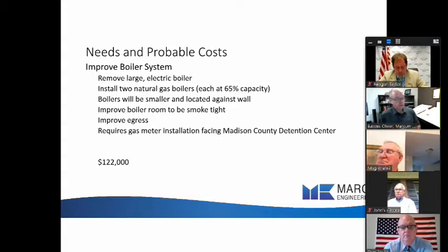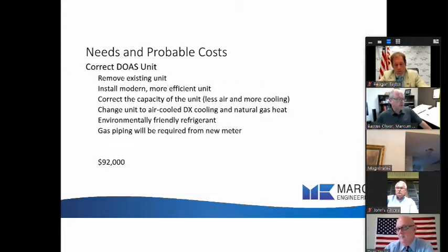The boilers will be smaller and they would be located against the wall, improving the egress and getting out of the NEC space requirements for the electrical panels. We'd also improve the boiler room to be smoke tight. And this would require a gas meter installation, and talking to the gas company, the best location we found for it was on the side of the building, the corner closest to the courthouse, and the meter would actually face our county detention center. So it'd be right along the sidewalk facing the detention center. To do this improvement to the boiler system is $122,000.